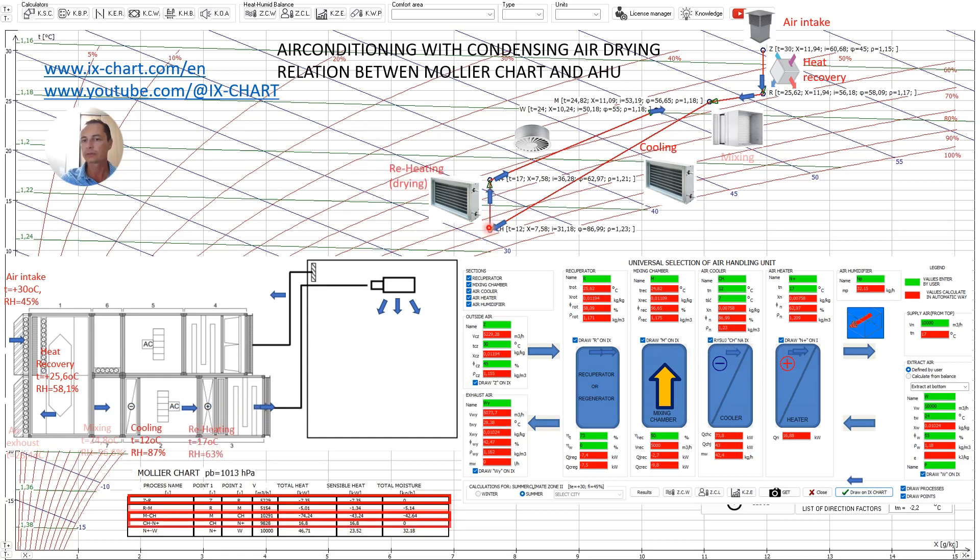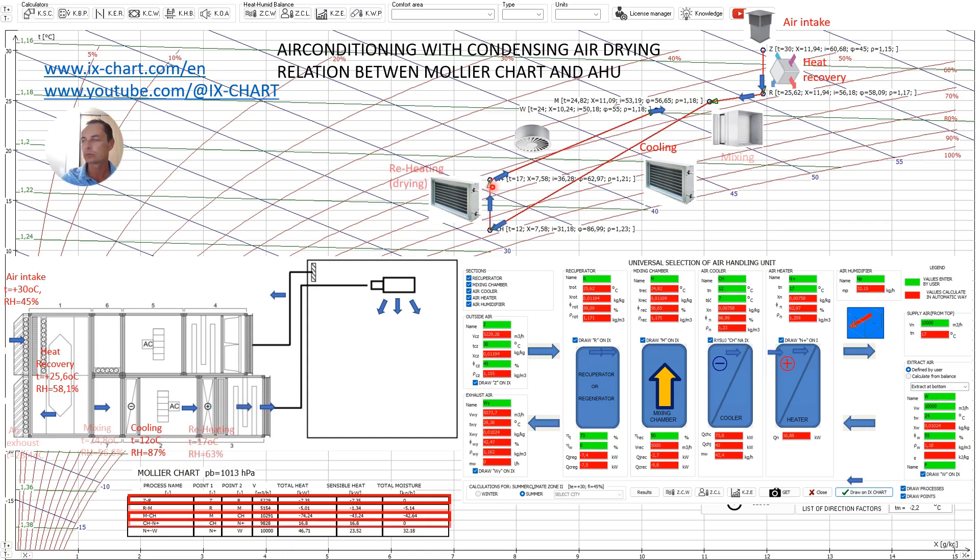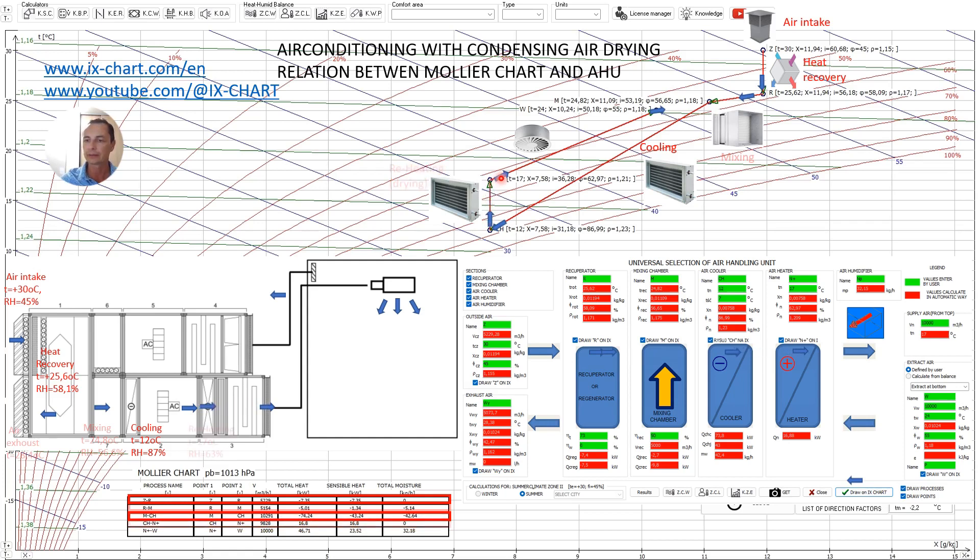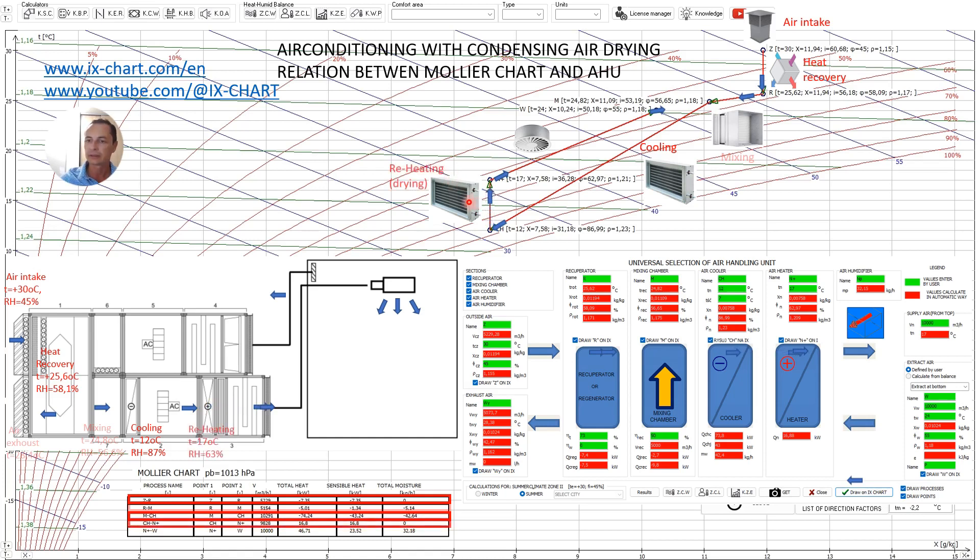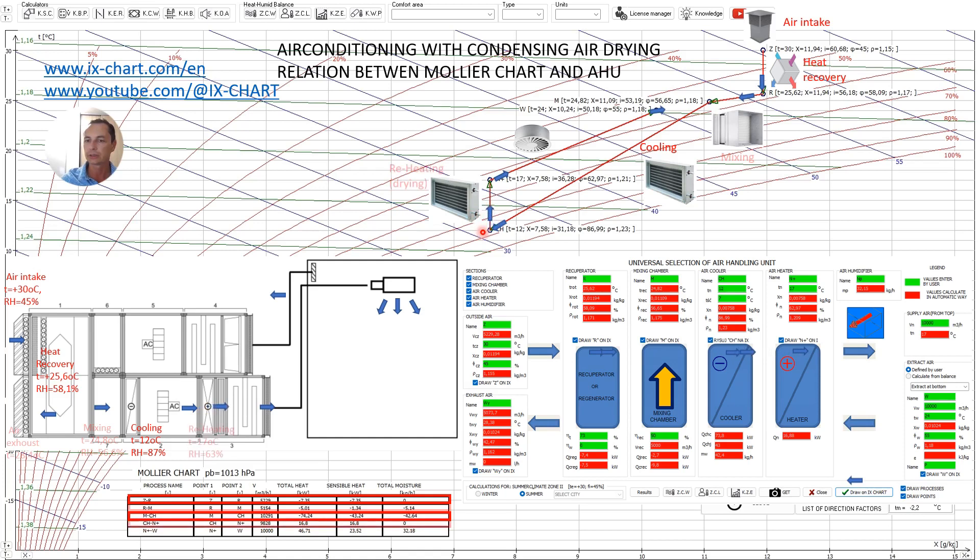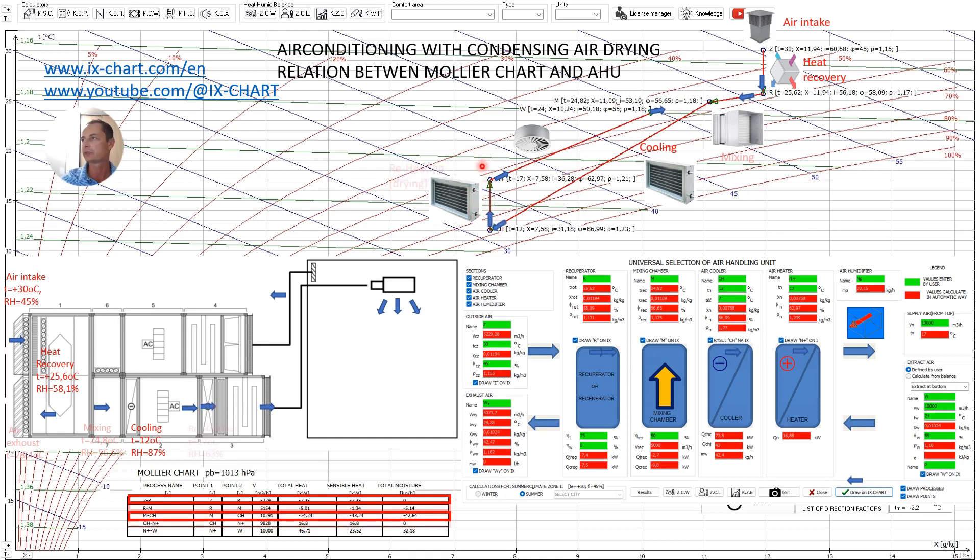Then after the deep cooling to avoid supplying air at such low temperature that could lead to discomfort in the room and an inability to maintain the required relative humidity we have to heat this air. We achieve this in heating section. The heating also occurs along a vertical straight line from point CH to N and this indicates that we exchange only sensible heat without moisture.